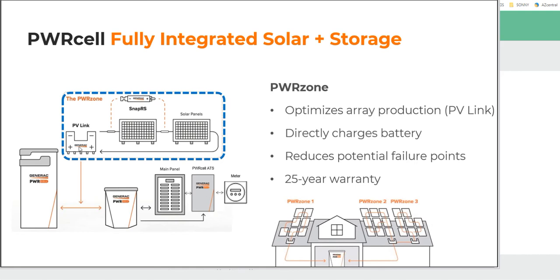We're a boost converter. So we take low voltage. We can go as low as 60 volts on this sucker. And we boost that up to bus voltage. And then we either push it into the battery or we push it into the inverter and flip it to AC and push it out. So that's an important distinction, because if you shade a string on a string inverter, that string's going to stop. If you've got 9 modules connected to a PV link, you can shade 7 of them, and this device is still going to deliver power back to the inverter.